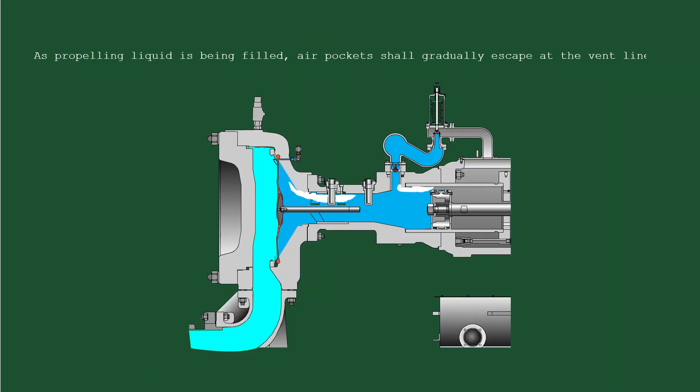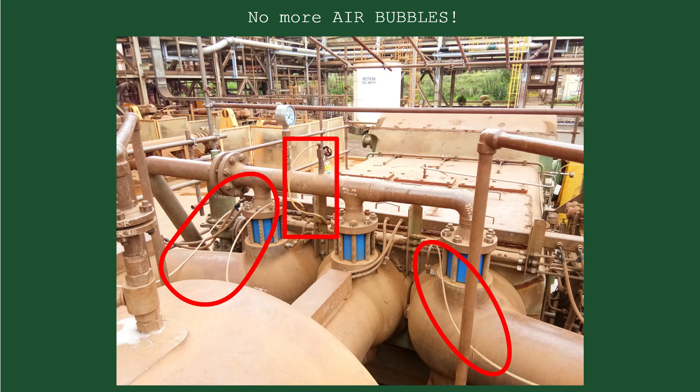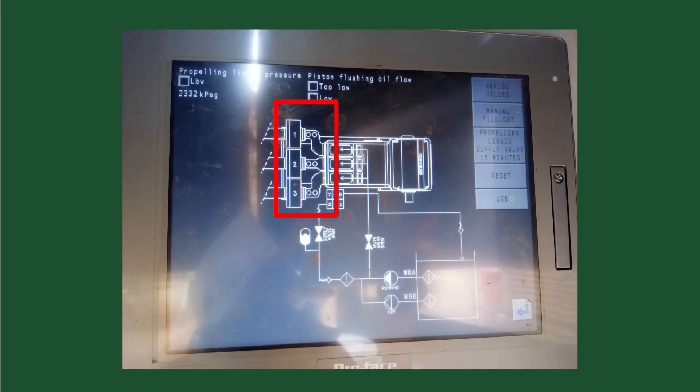As propelling liquid is being filled, air pockets shall gradually escape at the vent lines. Close the vent valve if there are no more air bubbles observed at the vent line and if the monitoring rod of the respective diaphragm deactivate the ZSL indicators.